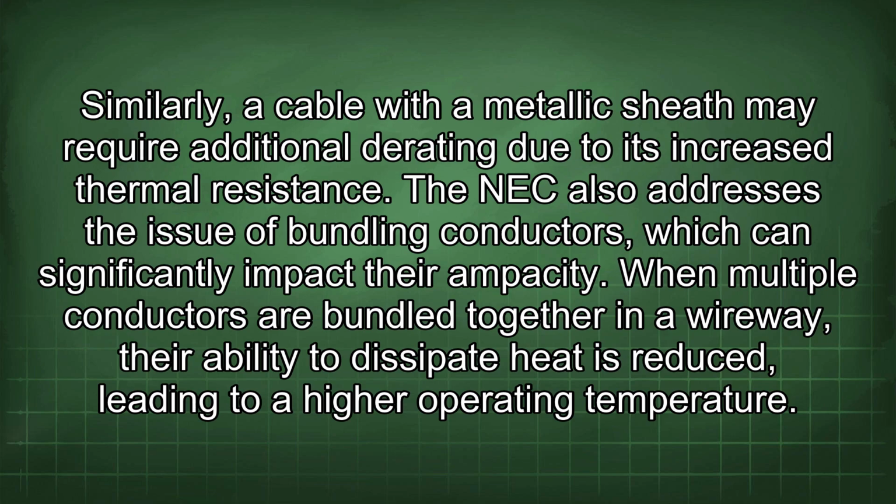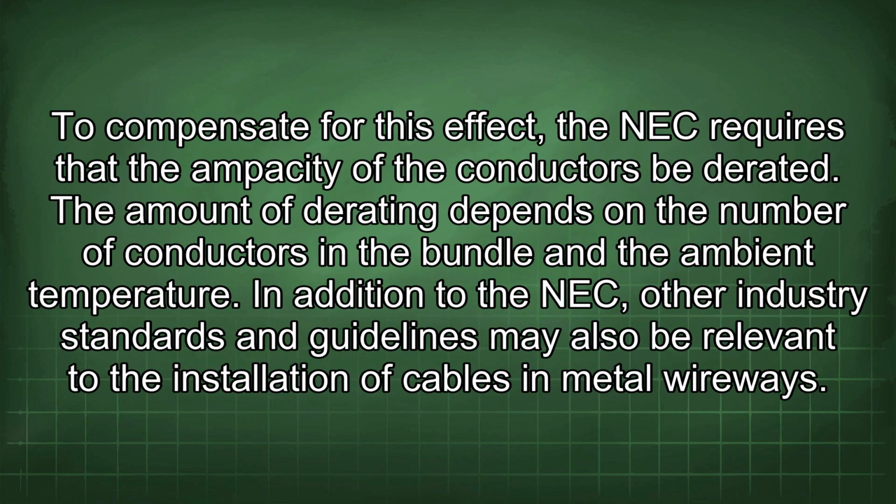The NEC also addresses the issue of bundling conductors, which can significantly impact their ampacity. When multiple conductors are bundled together in a wireway, their ability to dissipate heat is reduced, leading to a higher operating temperature. To compensate for this effect, the NEC requires that the ampacity of the conductors be derated. The amount of derating depends on the number of conductors in the bundle and the ambient temperature.